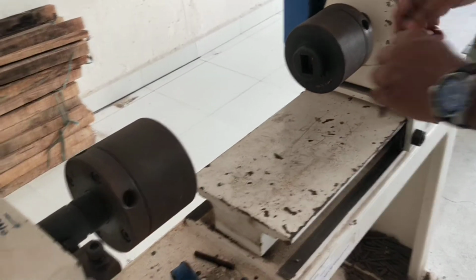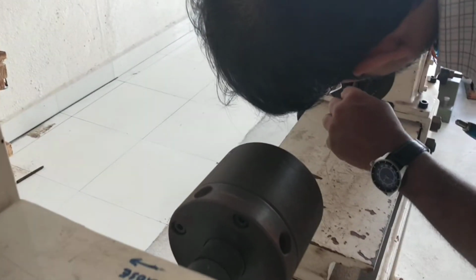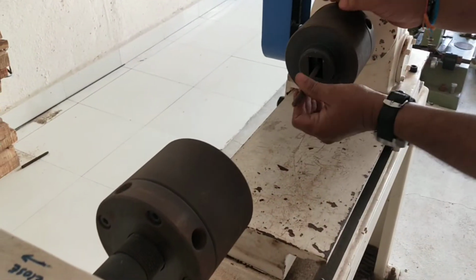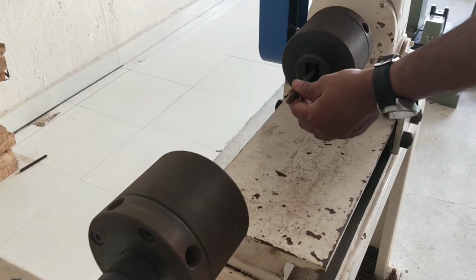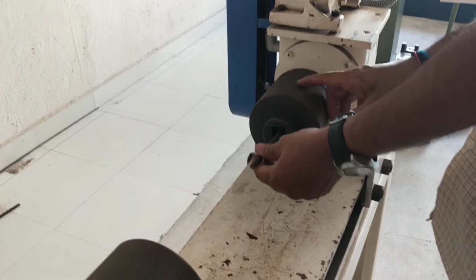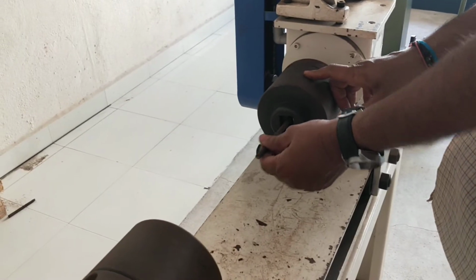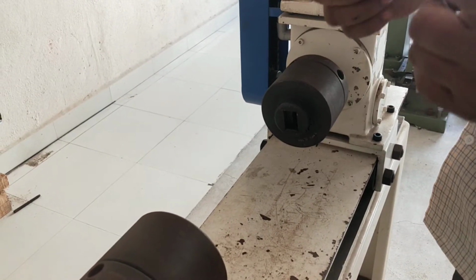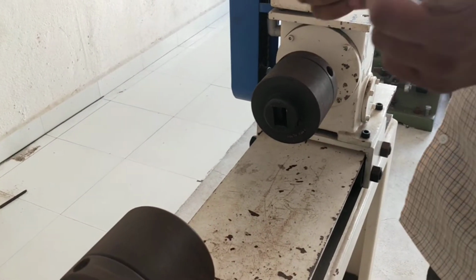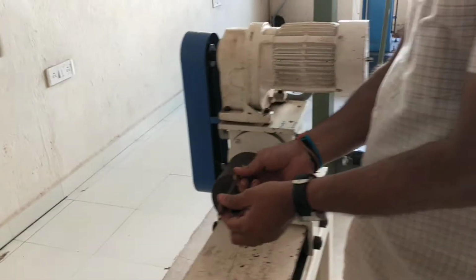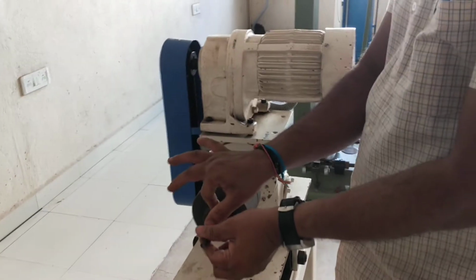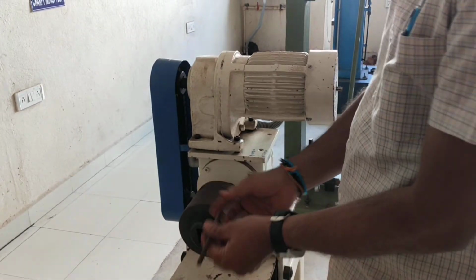You got the vertical position. Now you just fix it. It will not go beyond a certain length. That length is a standard length, 31.5 mm. The length of this test piece is 143 mm. So according to standards, it will fix the testing length automatically.